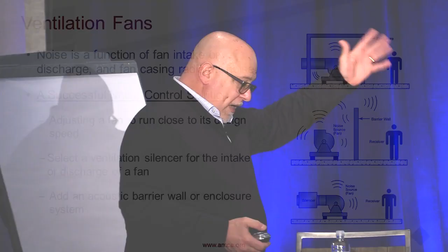If you look at the ventilation fans too, you can do a couple different things. You can see we looked at the casing radiated noise, the fan intake and discharge noise. The top picture there would be an enclosure, a sound enclosure around the fan. You want to make sure that enclosure is ventilated properly based on the horsepower of the fan. And then if you have to put in some inlet areas or a fan-powered exhaust just to ventilate the heat, you want to make sure those sound paths are quieted with silencers.